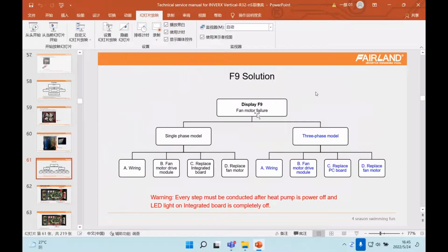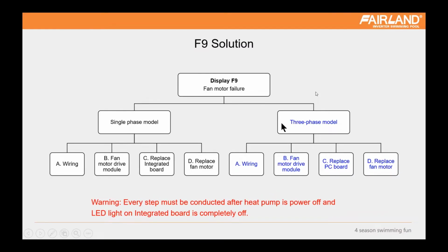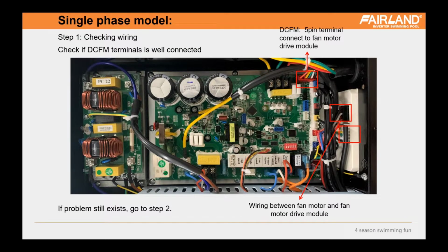F9 is fan motor failure. It's about the whole ventilation system: the wiring, the fan motor, the drive module, and the integrated board, which offers power, and finally the fan motor. Any problem with the fan motor, you need to check these four parts with these four steps.